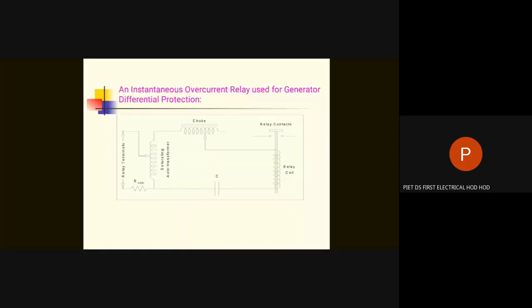And you have to have the correct value of the knee point voltage, that is, the knee point of the CTs. VKPV should be IF into RCT plus RL. So if you buy good CTs, then the saturation of the CTs will not be a problem. Right. So this kind of a relay is used.